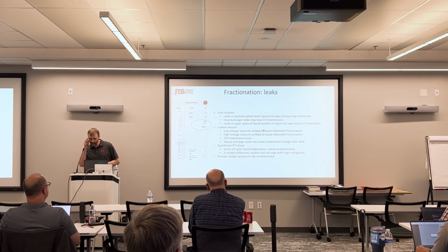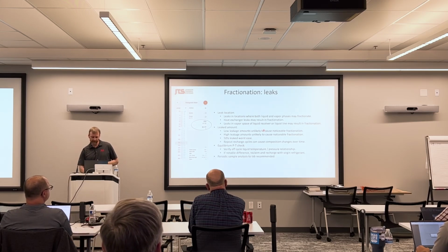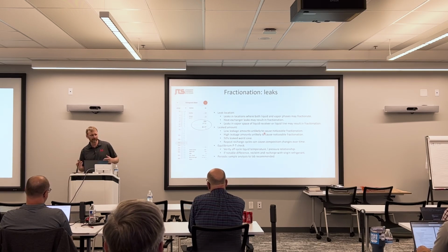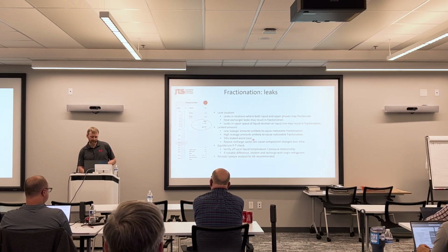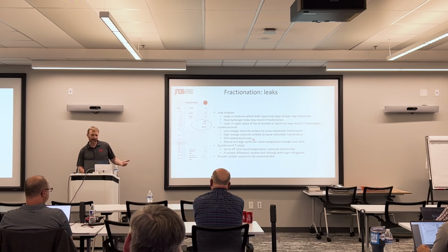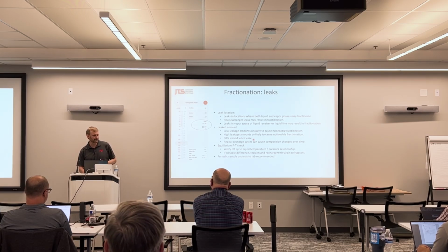Another thing to consider is leakage amount. Low leakage amounts are unlikely to cause a noticeable difference. Let's say you lose 10% of your refrigerant charge, you come back and top it off with 10% new virgin refrigerant. You're not going to change the composition that much. High leakage amounts are very similar. Say you lose 90% of your charge, and you come back and top the system off with 90% virgin refrigerant, your composition is still pretty close to what the refrigerant manufacturer originally designed. Worst case scenario is about a 50% leak rate. If you leak out half the charge and come back and top it off with another half charge, your composition is going to end up being a little different.